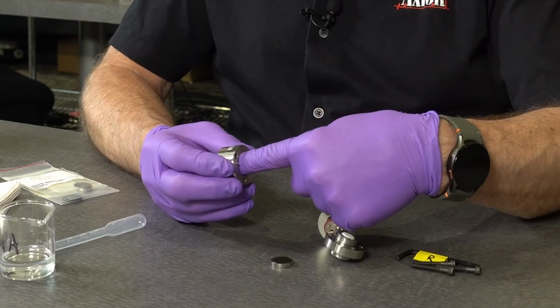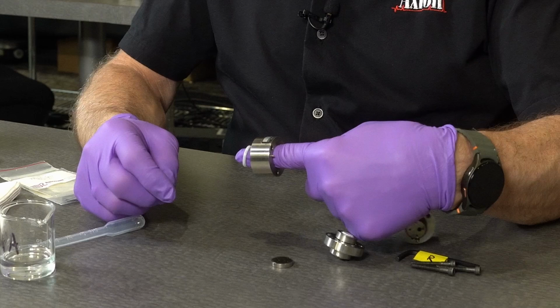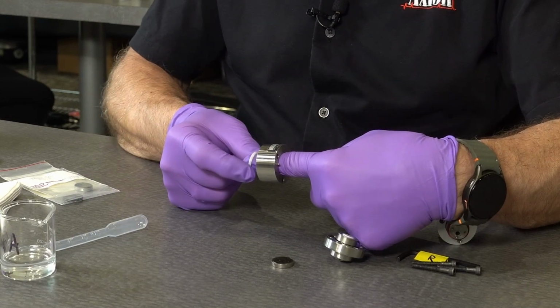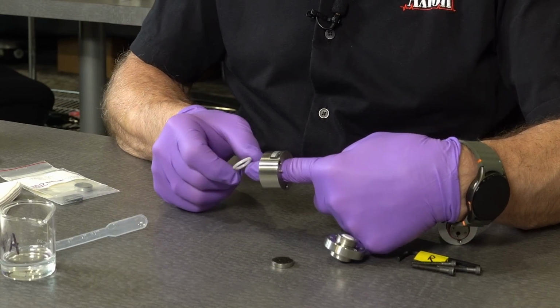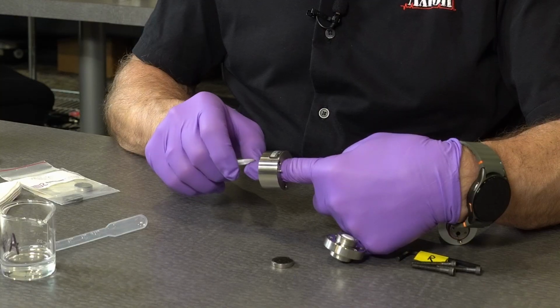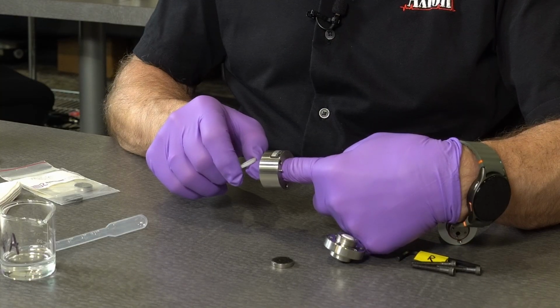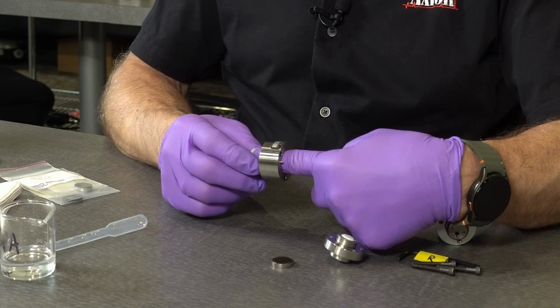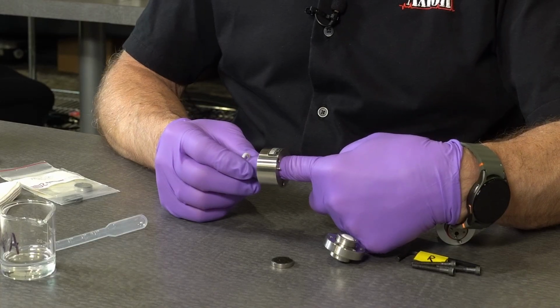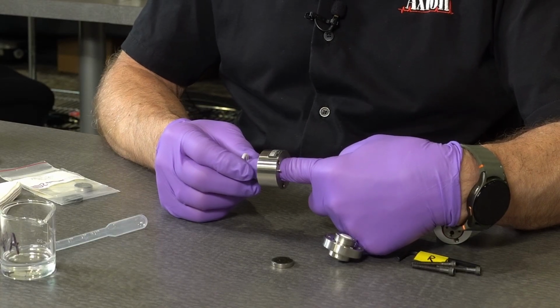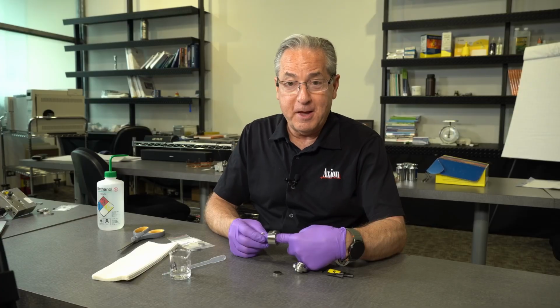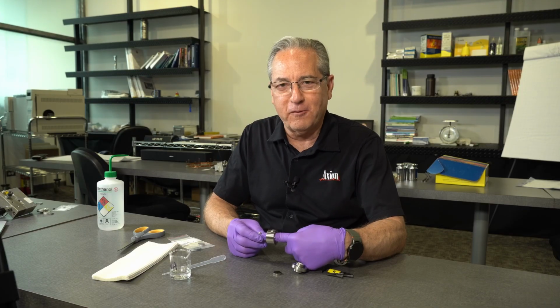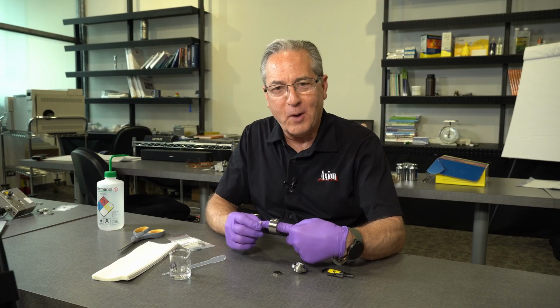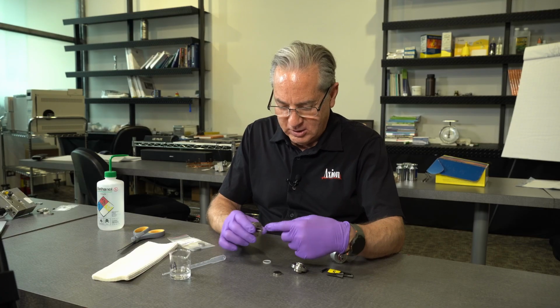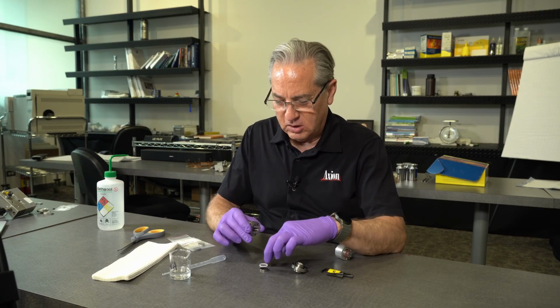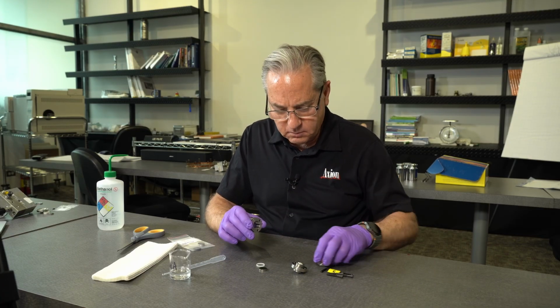If you stick your finger in, you see what came out the other side? That's called the isolation seal, and it's a pump seal. There's a spring inside. What's funny is I've never seen it come out when you tap it, and unless you know it's there, you're not going to be able to find it. So my trick is to stick your finger in there, and your finger will grab it and it'll come out. Okay, so these are the 2 parts that we're going to replace.